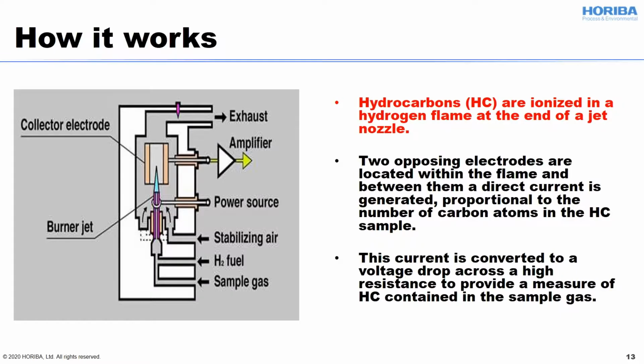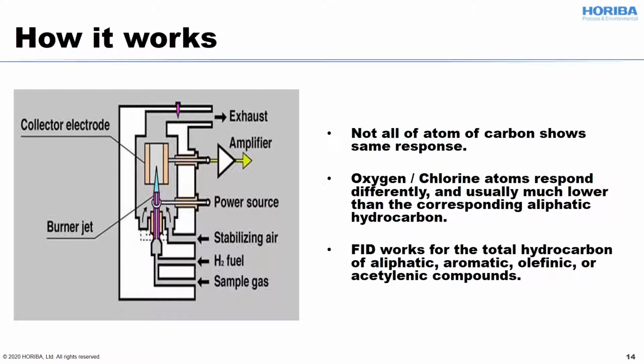This method provides a total hydrocarbon result as if all carbon atoms are from aliphatic, aromatic, olefinic, or acetylenic compounds, where the detector response caused by these atoms is approximately relative to the number of carbon atoms present in a molecule. Other types of molecules, including those containing oxygen or chlorine atoms, will respond differently, usually much lower than the corresponding aliphatic hydrocarbon. Therefore, other methods must be used to determine the exact constituents of the total hydrocarbon response. Anyway, FID is good to see the trend of total hydrocarbon, and if you want to see each component precisely, then GC-FID will be another method to achieve that result.